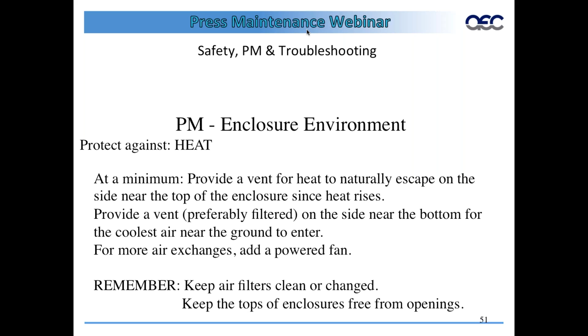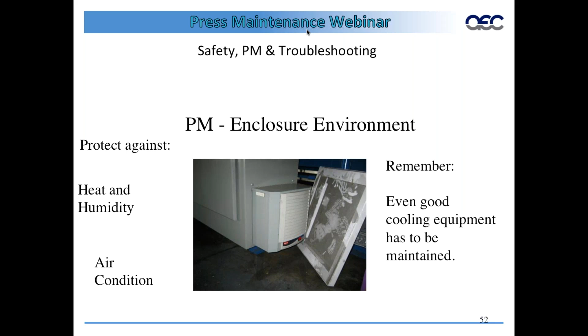Here's a picture of a panel with a good air conditioner on it to decrease heat and humidity around the components. But if you don't manage the maintenance on the air conditioner, I've pulled off so many guards with filters so dirty that you're actually putting hot air back in. So just because you have air conditioners running doesn't mean they're doing the job. It needs proper preventive maintenance.